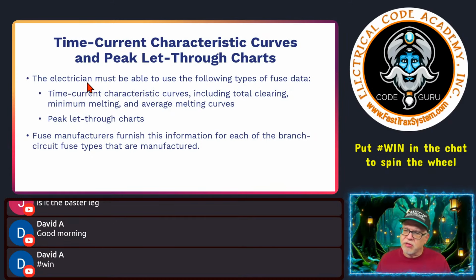Okay, so electricians that have that task at hand have to understand the time-current characteristic curves, including total clearing, minimum melting, and average melting curves. Again, we're talking fuses, and the peak let-through charts. Fuse manufacturers will furnish this information for each of their branch circuit fuse types that are manufactured. So a lot of the manufacturers, if you're going with Cooper Bussmann, for example, and you're using fuses, they have documents, they have books, they have all the information you need. Please, folks, don't try to act like, I'm smarter than somebody else, I don't need to ask somebody else. Guys are famous for that, right? We get one of those new ceiling fans, and the first thing you do is throw out the instructions.